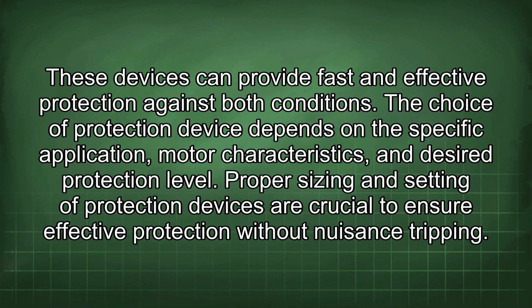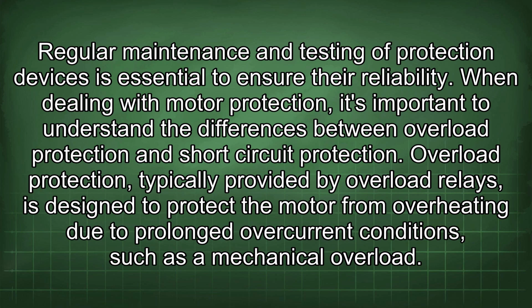The choice of protection device depends on the specific application, motor characteristics, and desired protection level. Proper sizing and setting of protection devices are crucial to ensure effective protection without nuisance tripping. Regular maintenance and testing of protection devices is essential to ensure their reliability. When dealing with motor protection, it's important to understand the differences between overload protection and short-circuit protection.